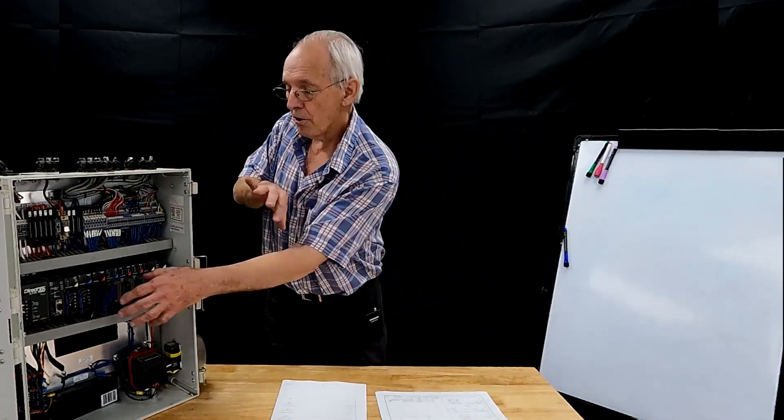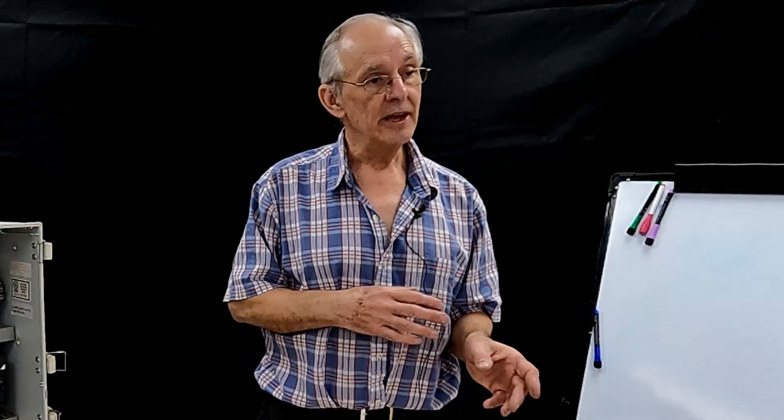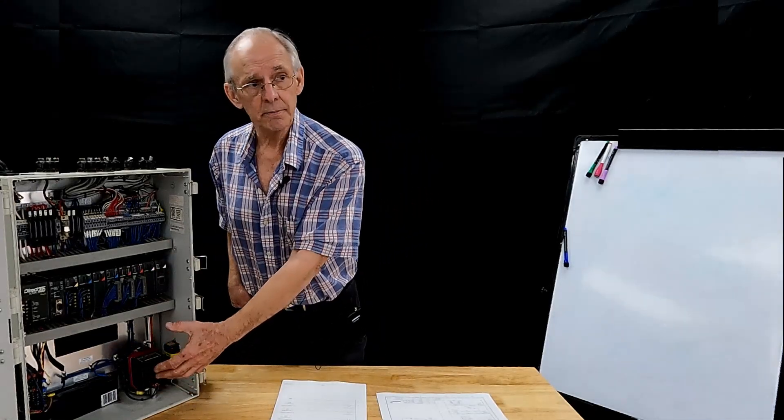You don't just fit parts into a panel where they'll fit. You try to look at the wiring. So if the outputs are on top, I tend to put the PLC at the bottom of the panel. It's an interactive process.